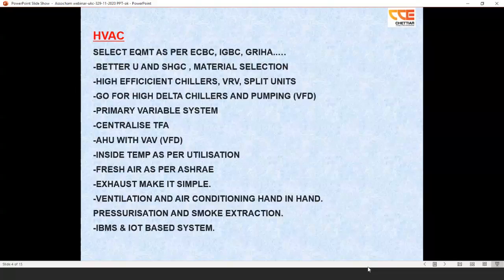And for a hotel or commercial building, as we said, there are energy saving factors like AHU with VAV units, and VFD you can go for. The inside temperature is very important. At the time of designing, it's very essential for the consultant to recommend to the client where the inside temperature has to be maintained, for example, a corridor can be designed for a higher temperature as compared to the guest room or office occupied area. By which you will be able to save a good amount of power consumption.